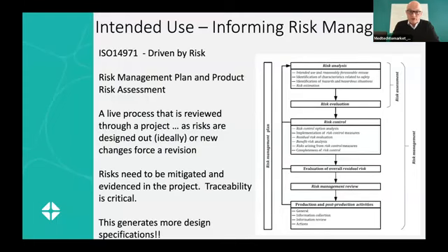As well as the design inputs, you have to consider risk. I mentioned risk management, ISO 14971. Basically, risk assessment is understanding, once you know who your customer is, where it's going to be used, etc., you can then generate a risk management plan based on how severe the technology is, whether if it was a misdiagnosis, how much hazard or how much harm would be caused, what the likelihood of that is.